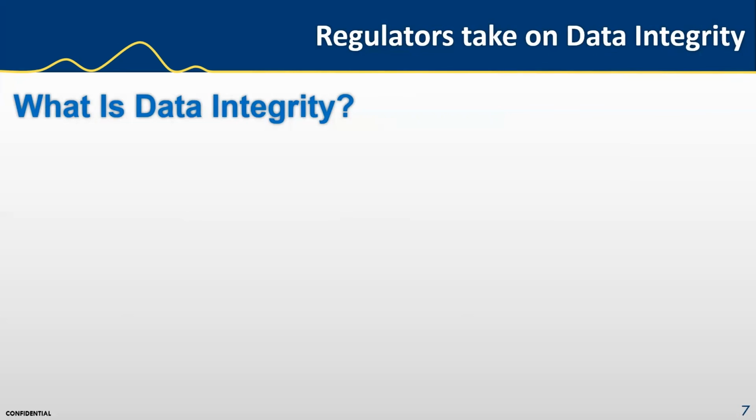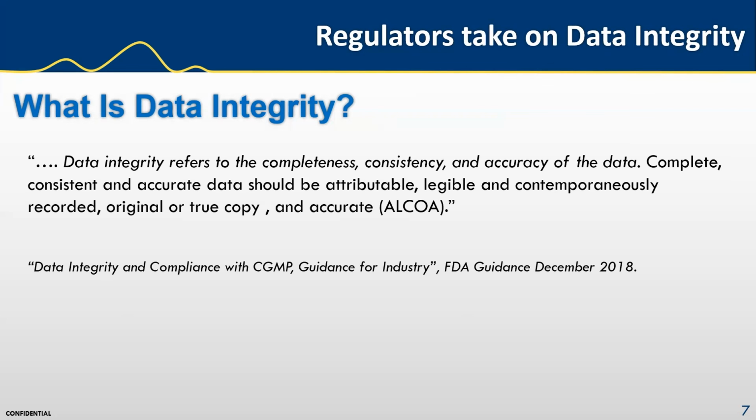What is data integrity? So what is all this data integrity about? Well, the FDA released more clarification with ALCOA, which defines what the FDA is seeking. Data integrity refers to the completeness, consistency, and accuracy of the data. Complete, consistent, and accurate data should be attributable, legible, contemporaneously recorded, original or a true copy, and accurate. It's called ALCOA.